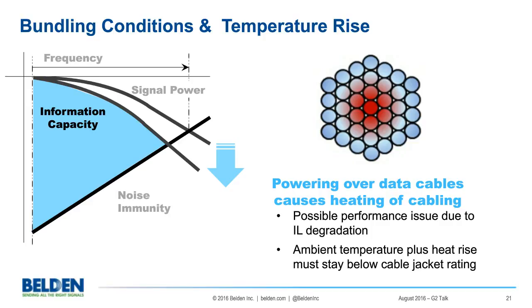This is what it might look like. The bundle is put together, and all of them have PoE power or current going through them, DC current, and the cables in the middle can get hotter because the heat can't get out. So as they get hotter, the temperature is going to increase, and that can cause the insertion loss to increase as well, as shown in this graphic. And it's important to know the ambient temperature plus the heat rise must stay below the cable jacket rating.